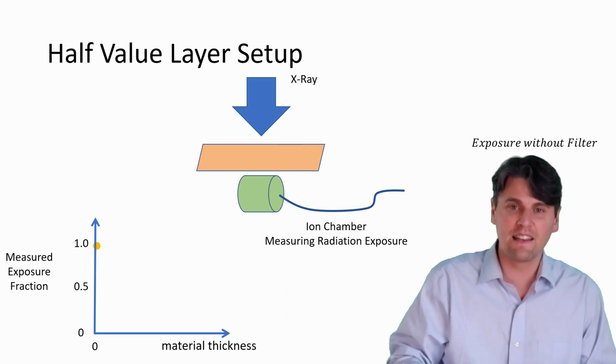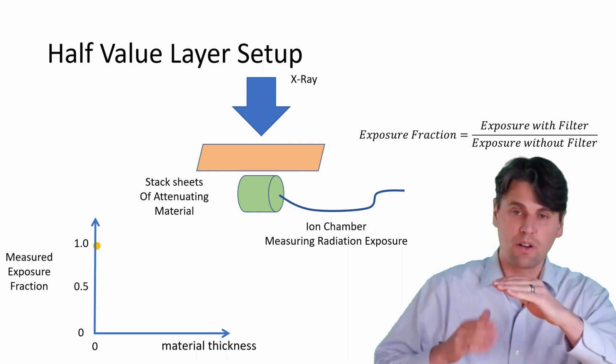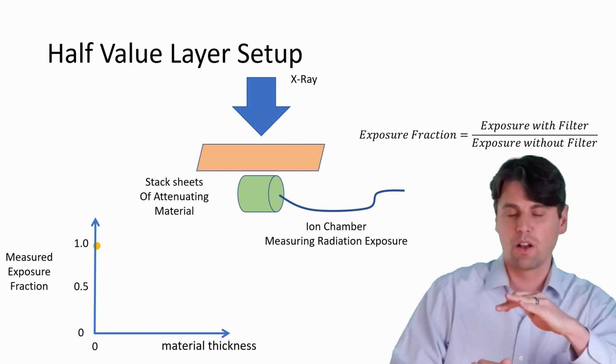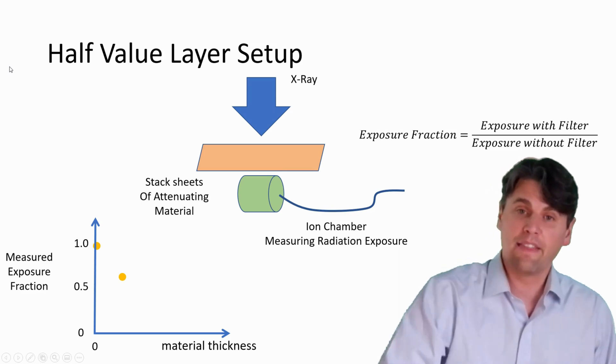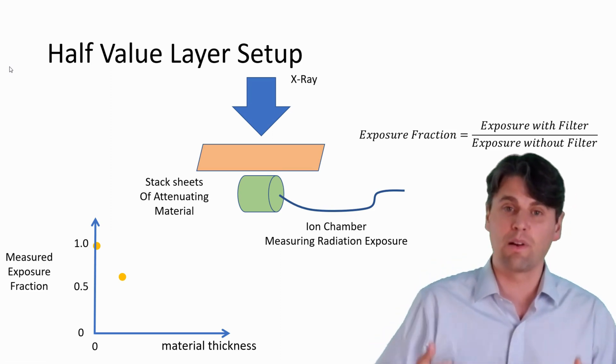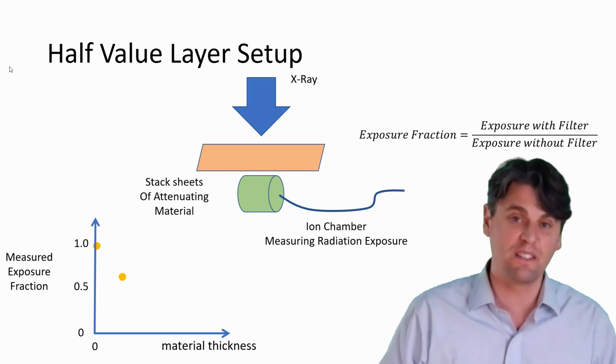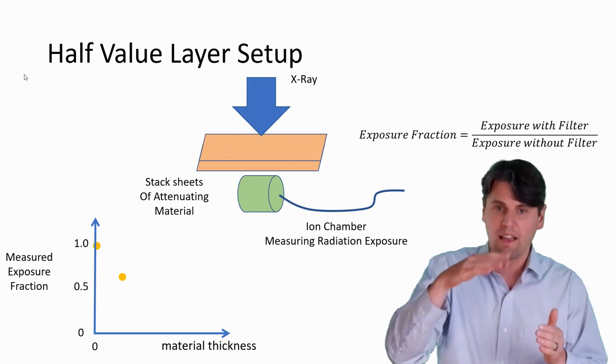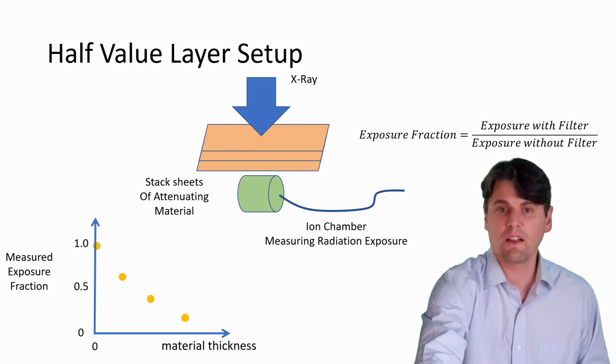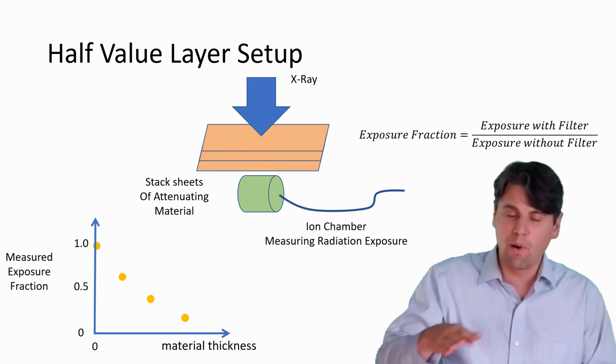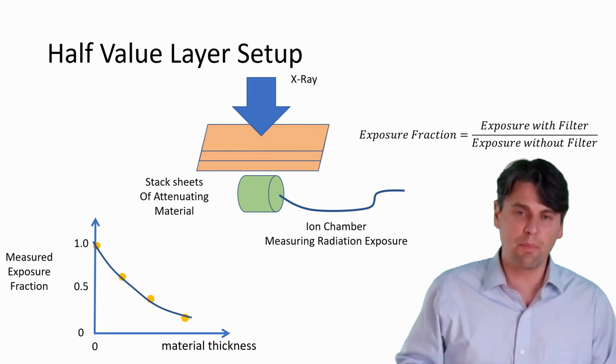Then we slide in a little bit of filtration there. We make a measurement again. And then we take the new measurement of the exposure divided by the original measurement of the exposure where there was no filtration. And then that'll give us a point on the curve. And the curve we're actually looking at is essentially the relative exposure on the y-axis. And on the x-axis, we're looking at the material thickness. Then we'll slide in another sheet and we'll get another point on the curve after we make a measurement. We'll do that again. And after we have a few of these measurements, you can see now that the points are actually making a curve.